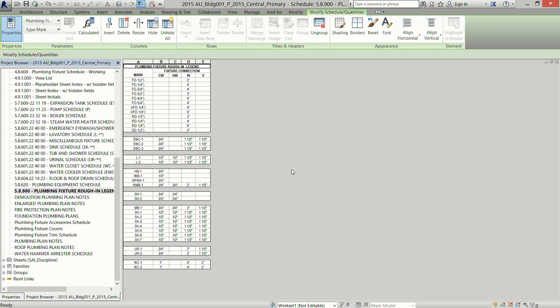One more thing that cut our tagging time significantly: we created a rough-in legend. All it does is pull the type mark for every plumbing fixture family we have, along with the waste, vent, hot, and cold connections. You plop that on the sheet, and there's no reason to tag every single rough-in pipe on your ISO anymore. On the ISO we were working on, that cut 45 minutes of tagging time. Once it's set up in your template, there's nothing else it needs — it automatically pulls the plumbing fixtures you have in your project.